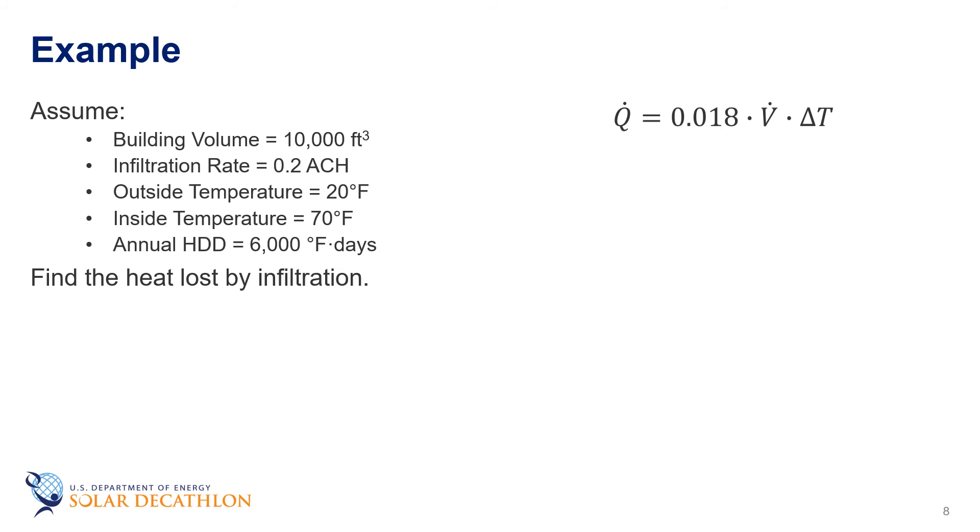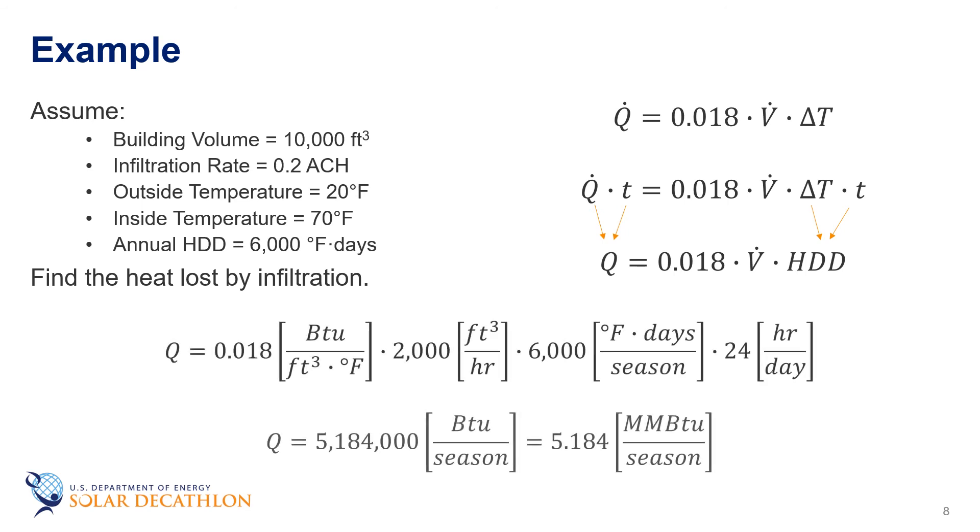We can also multiply both sides by time to get a seasonal energy impact, much like we did in one of our other building envelope episodes for conduction through walls for the entire season. Don't forget to convert with the 24 hours per day. The result is 5.18 million BTUs per season. This is the approximate amount of energy that would be required to heat the air infiltrating the building during the heating season. This is in addition to the energy required to replace heat loss by conduction through the walls and windows. And you may be wondering about the opposite example during the summer when it's hot outside. The approach for that example would exactly be the same as the one we just did. Just replace the heating degree days with cooling degree days to represent the cooling needed to cool the air because of infiltration.